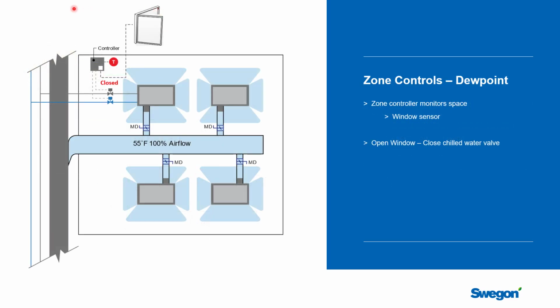So another thing that you'll see commonly done is, what if you're doing a more residential type space, might be a hotel or a dormitory or a retirement home, someplace that has windows, especially operable windows. And so you'll see that there'll be window switches added to those windows. And so instead of having a dew point sensor, you would have a window switch, and the moment that window is opened, you would turn off the chilled water valve and close it. And that makes sense.